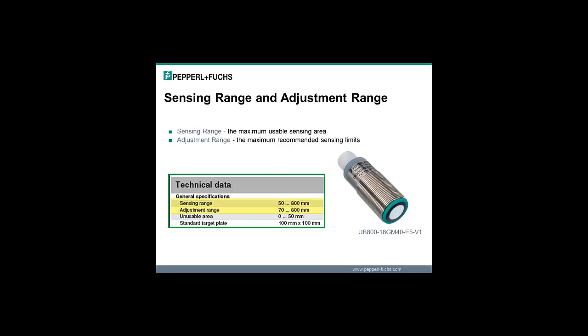If you're looking for a sensor, you want to know how far away it could detect a product. There are two different specifications that involve the sensing range. One is the actual sensing range, which is the maximum usable sensing area. The next is the adjustment range, which is our maximum recommended sensing limits. So for this UB800 model, the sensing range is actually 50 to 800, but the adjustment range that we recommend is 70 to 800.